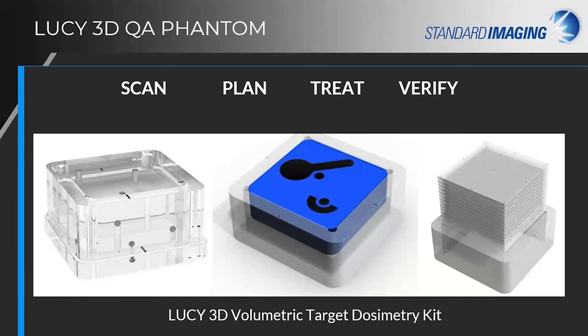And then using also, in combination with this insert on the bottom, you see here, the hidden Winston Lutz target, which is provided with the phantom. Also use that so you have your 5th target. And again, you can use a detector and or film at that central target to verify that plan. So I hope that answers that question.